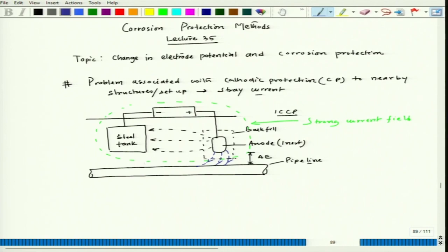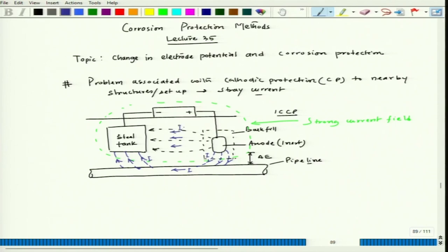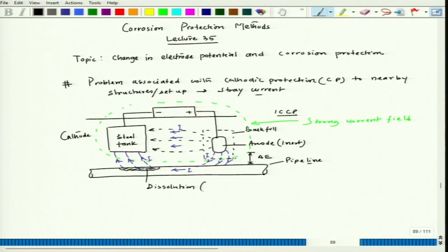Since the circuit has to be completed, the current would try to leave the pipeline surface around a certain zone and enter through another zone because of the potential difference. Wherever electrical current leaves a metallic object, that part is susceptible for dissolution. So that particular segment of the pipeline is susceptible for dissolution or corrosion.